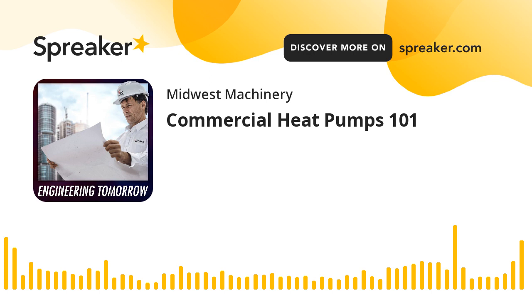VRF, though, offers close to the same efficiencies as water source heat pumps without the need for a cooling tower and water and pumps, because they're air cooled. So just like your house, they have condensers outside. They're very high powered condensers. And then they run the refrigerant lines like they do in your house throughout the building to the various fan coils that are in each zone. So that's what the VRF manufacturers will say: hey, you don't need a cooling tower, you don't need pumps, you don't need all these water lines. Just run some condenser lines back and forth from our unit. We'll give you pretty good efficiencies.